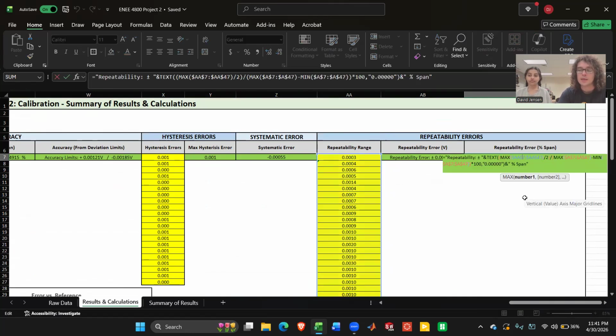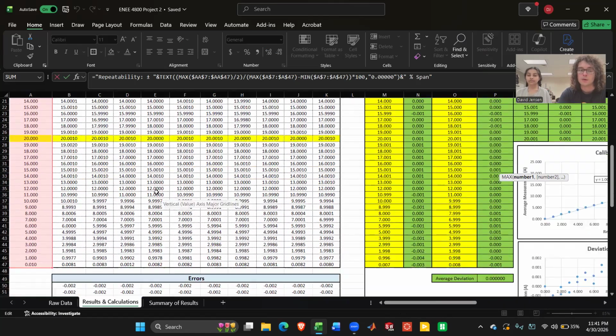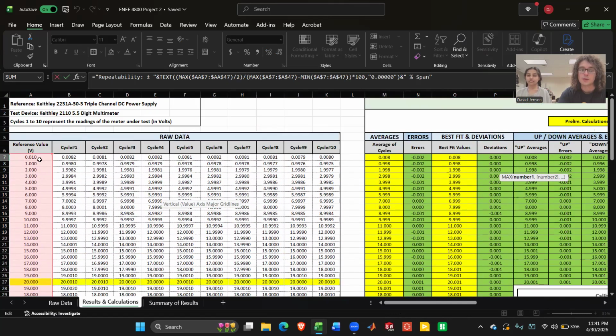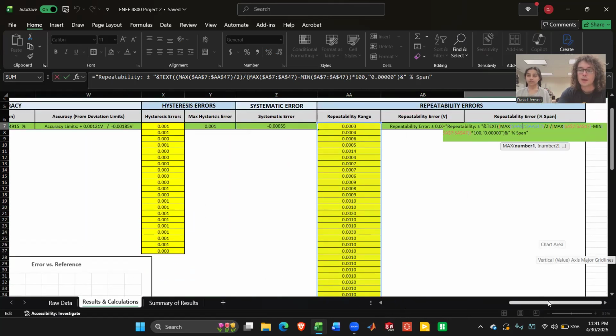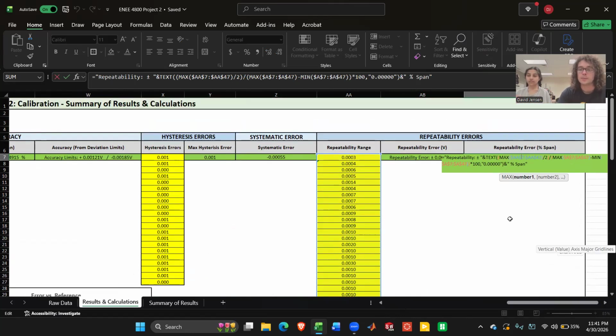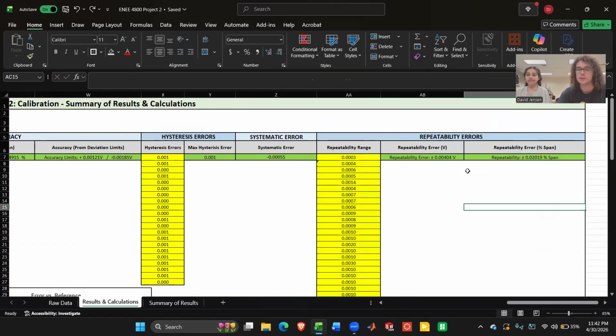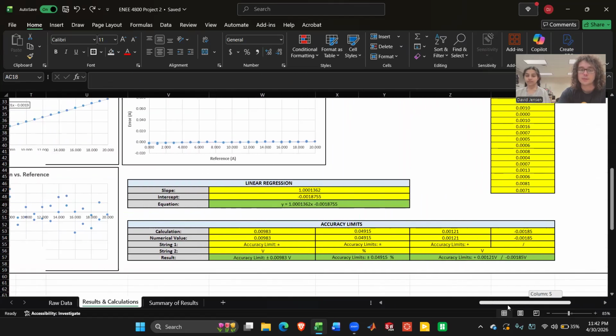And then to determine that as a percentage of the span, we took that same maximum, divided it by 2, but then we divided it by the maximum minus the minimum of our reference values here. So the largest difference between the two reference values. And then we multiplied that by 100, which again just gives us our span. That's just 20 minus 0.01. So that normalizes it, and then we multiply it by 100 to get the percentage. So as you can see here, our repeatability error in both percentage and absolute value is very low. It's very strong results for this process.